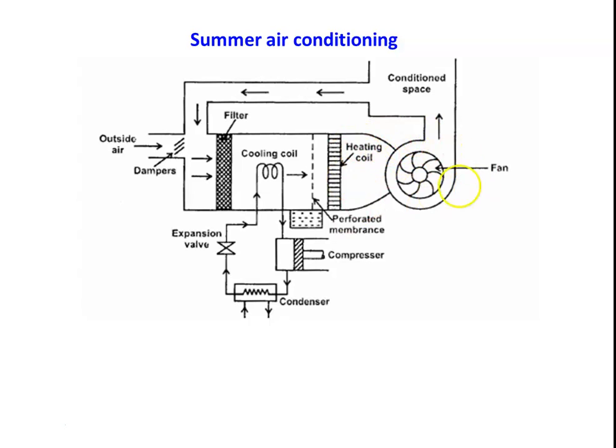Then the air is circulated through the fan to the air conditioned space. So this is the summer air conditioning system. And the year-round air conditioning system is a combination of these two. So there will be a heater, a cooler, a humidifier and a dehumidifier. All the equipment is assembled together. Based on the outside temperature conditions, we control the required equipment and operations, and we produce the air conditioned air. So year-round air conditioning is an assembly of the two systems.